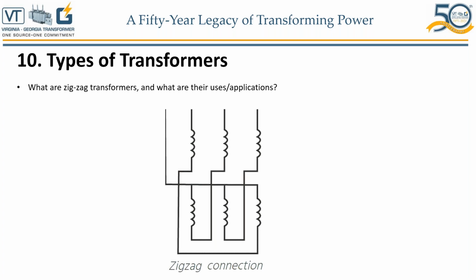How they are designed is that the first coil on each zigzag winding core is connected crosswise to the second coil on the next core. The second coils are then all tied together to form the neutral, and the phases are connected to the primary coils. Each phase therefore couples with each other phase, and the voltages cancel each other. There will be negligible current through the neutral point, as zigzag has a high positive and negative sequence impedance with a low zero sequence impedance, which can be tied to ground. So that's what the zigzag transformer is, and that's its application.